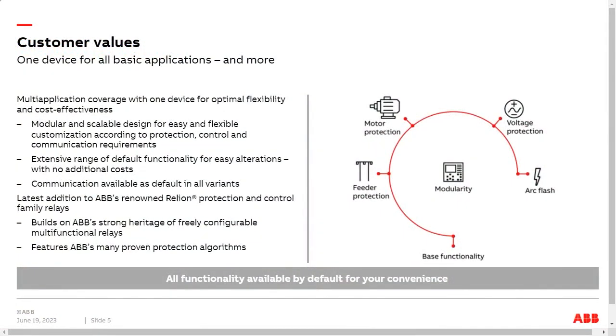Let's take a look at some customer values. Well, it's multi-application coverage with one device for optimal flexibility and cost effectiveness. If you remember, many competitors have dedicated devices for applications. In case you're interested in feeder protection, you need to buy a certain product, voltage protection another one, and maybe motor protection a third one. With this multi-application approach, the idea is that with one device you can easily select what application you wish to run on it. Of course this also reduces the amount of spares needed. It's modular, so depending on what modules you insert into the device, you can adapt the device to the need.